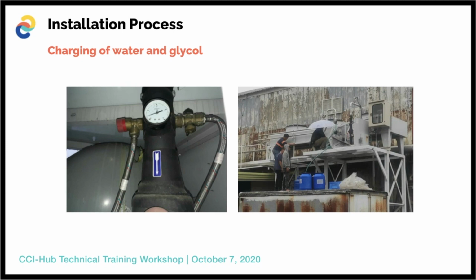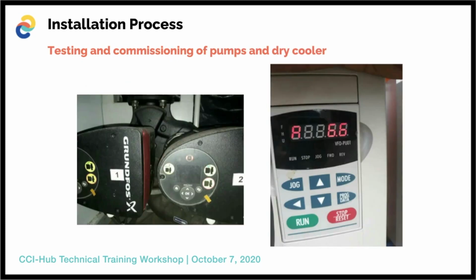The next procedure is testing and commissioning of pumps and dry cooler. As you can see in the picture, on the left side, this is a Grundfos Magna twin pump, which is programmed to auto-adapt settings for cut-in and cut-out operations, depending on the needed load demand, with 12-hour rest intervals on each pump motor. This is a fully inverter pump motor with variable speed controllers. On the right side of the picture, you can see the VFDs in the dry cooler. This is also programmed to run about 0 to 80 hertz with a liquid temperature controller with automatic and manual functions in case the VFD fails to run.